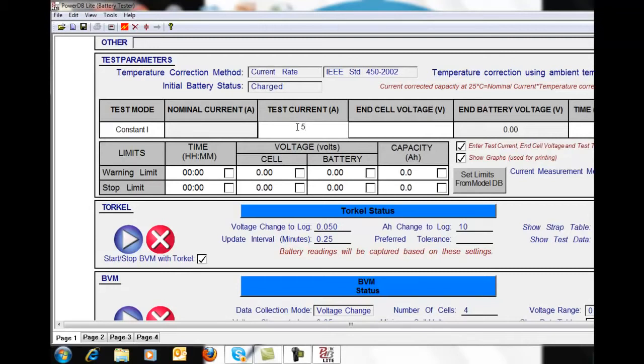I'm going to discharge at a rate of 50 amps. And I'm going to bring each of the jars down to a cutoff voltage of 10.5 volts. And notice that Torkel will automatically take the 10.5, multiply it by the 4 jars that I told the Torkel that I'm testing, and my end battery voltage will then be set to 42 volts.